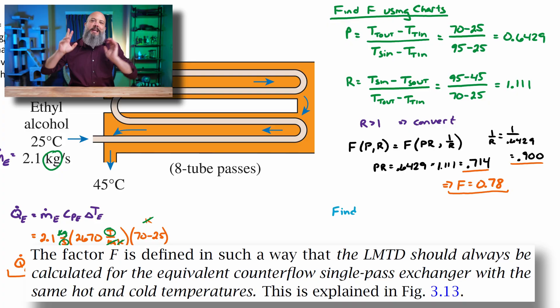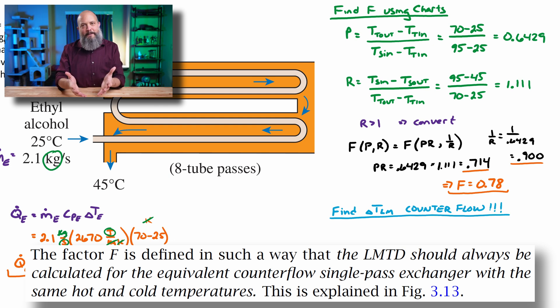All right, two steps down, delta T_LM, last part. This has to be the counterflow LMTD equation, right? The shell and tube design is not parallel flow. The water and the ethyl alcohol kind of have their inlets and outlets matched up.